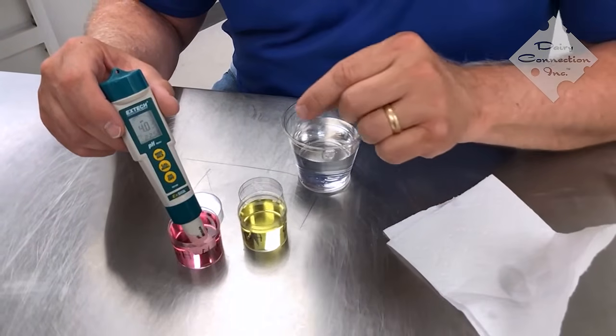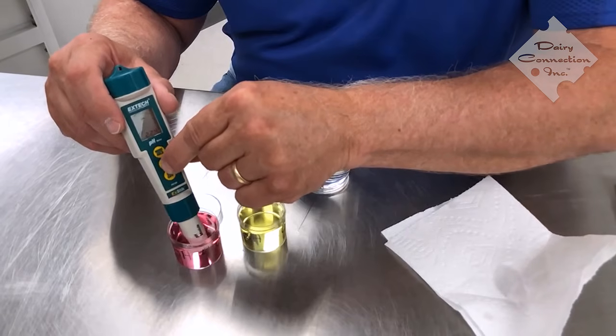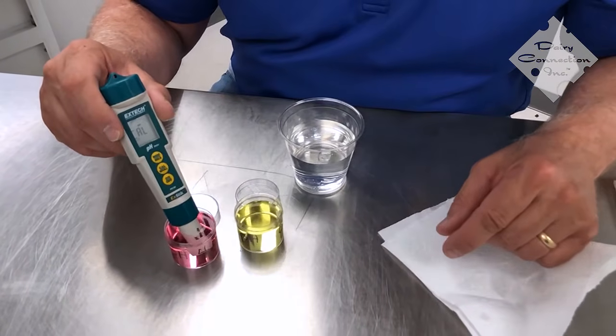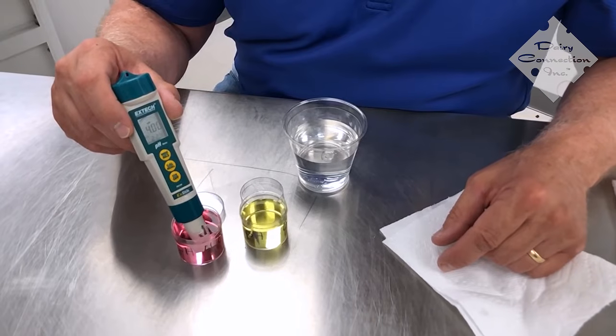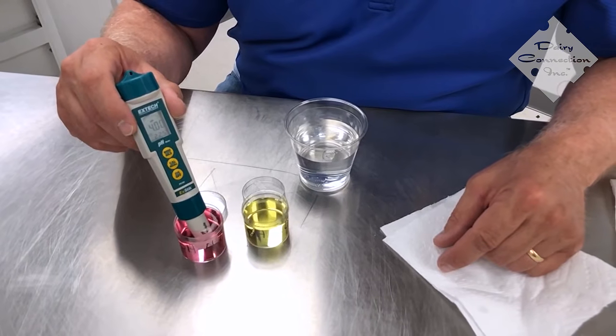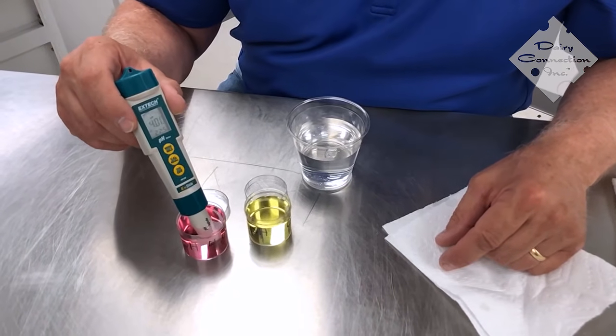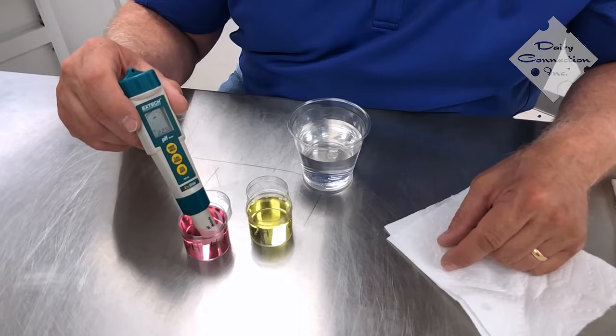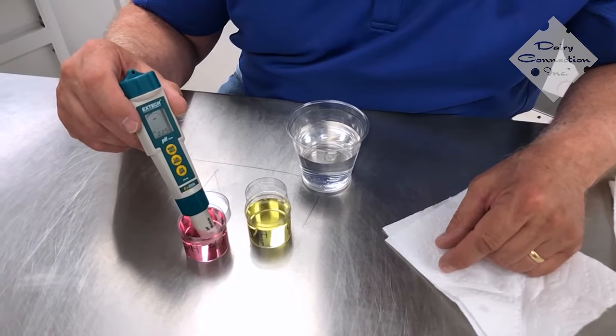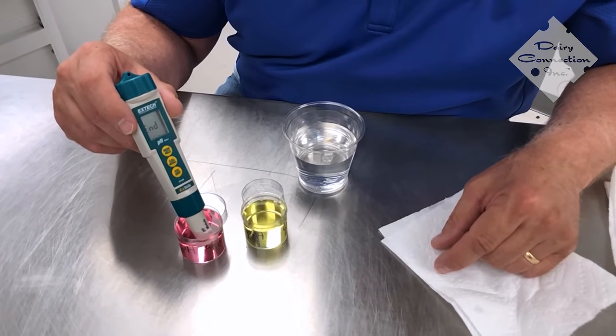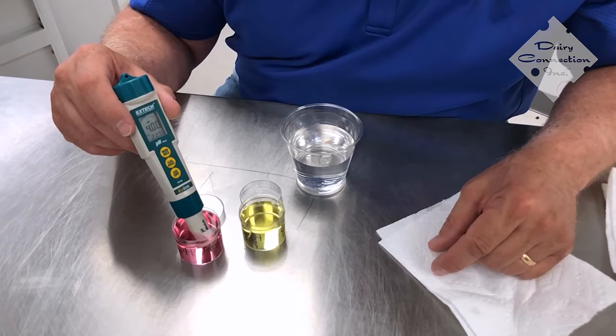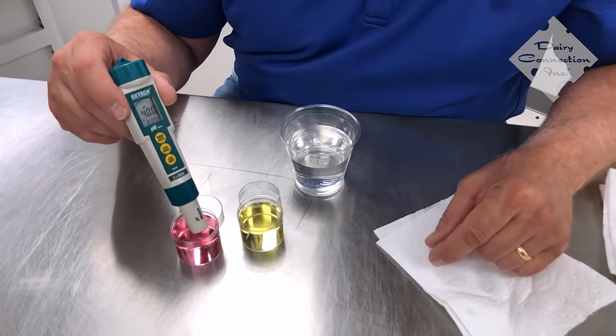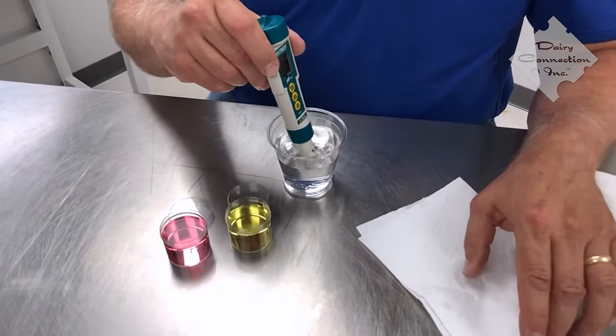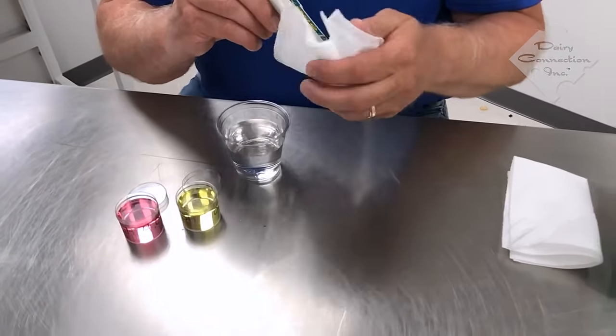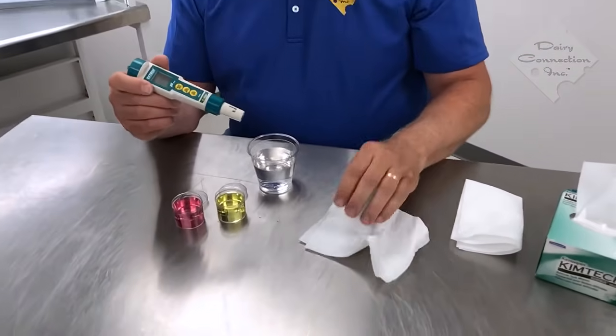place it in the 4 buffer, and again, repeat the step of pressing in the calibration. It is now going to calibrate down to the 4 pH, so that we'll end up with an accurate measurement from 4 to 7. And again, it goes through this process until it reaches an equilibrium, and then the end will come up, and then it goes back and standardizes. Once that is reached, you can rinse it off. And at that point, you are ready to start measuring.